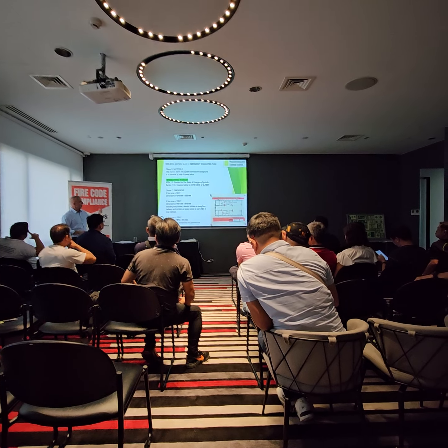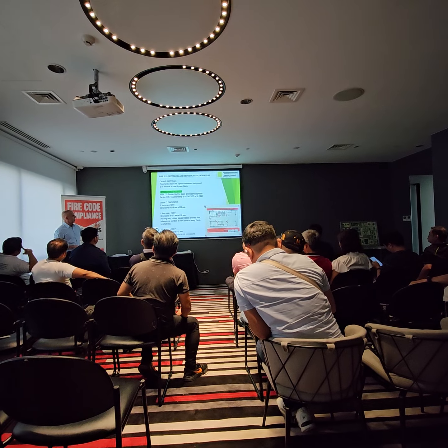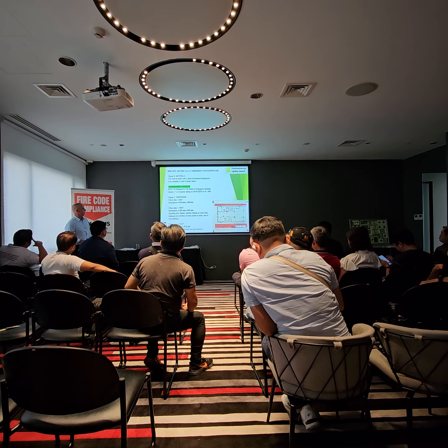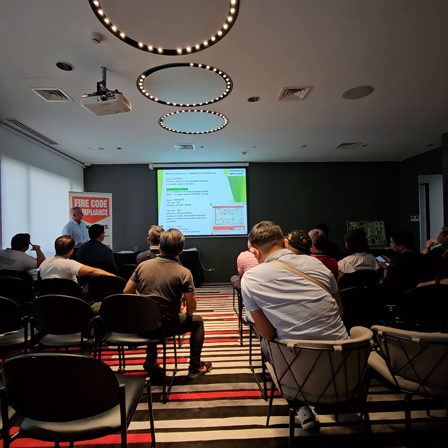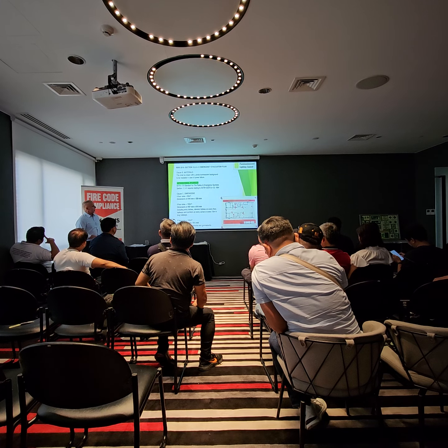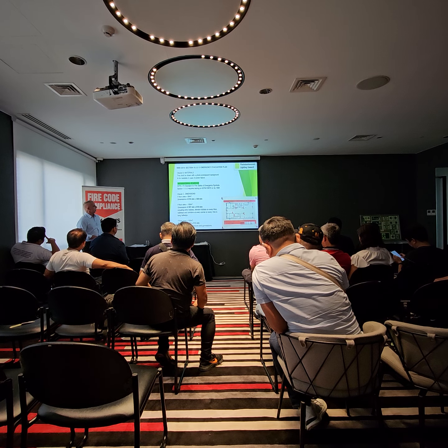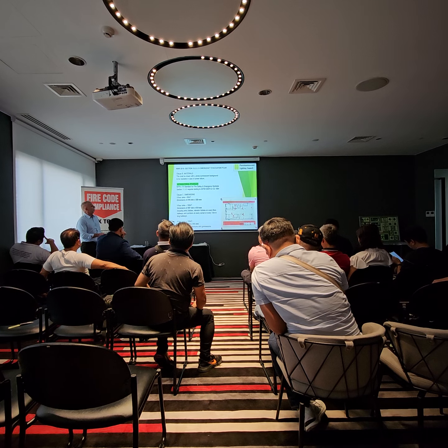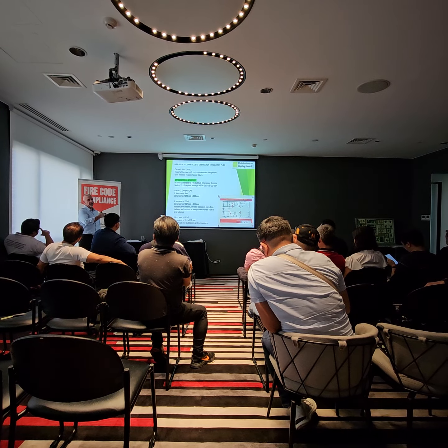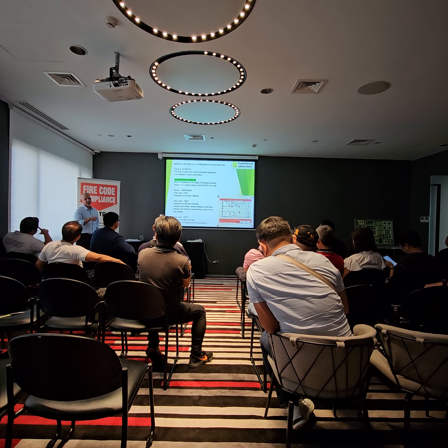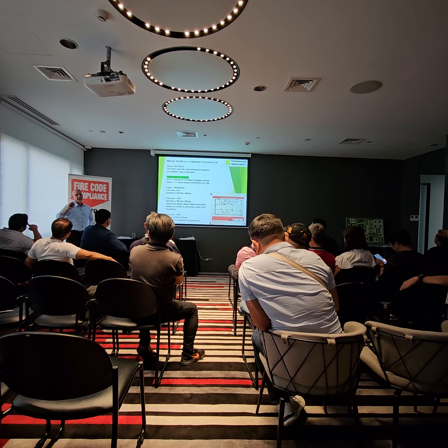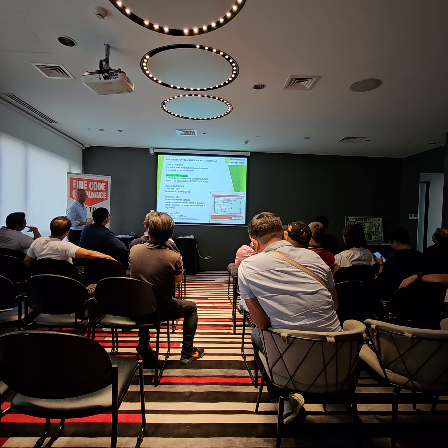And what we've put as a proposal is to say, well, okay, if it's over 150 square metres, say it's 200 square metres, if you can't put one of those in, put 4 of those in different places, and it makes a lot more sense in terms of getting people out, not just to have one big one somewhere, but have them dispersed throughout the area.